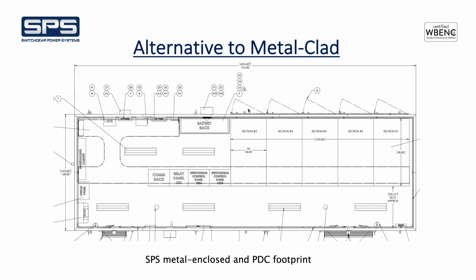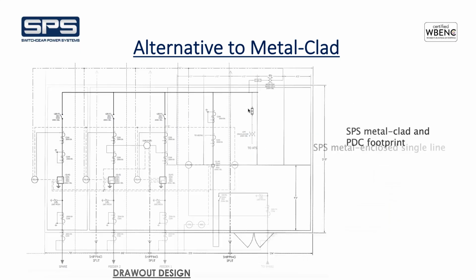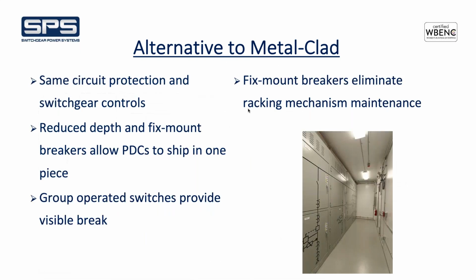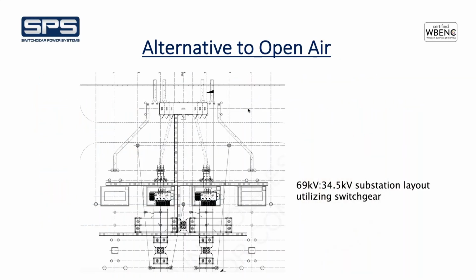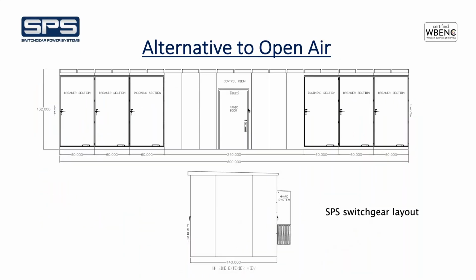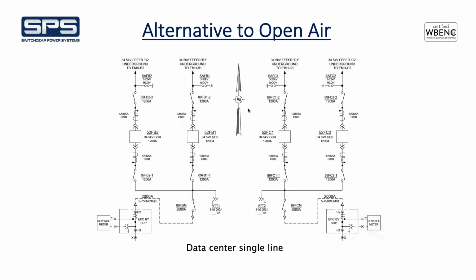The answer is, the footprint to have a line side disconnect would get a little bit deeper than the 98 inches. So in order to have 2 disconnects per breaker, which would be what this design was. This is 2 disconnects, and it went to 140 inches. Part of that was, I believe, driven by the size of the control room that they needed. So we front and rear aligned everything. But yeah, this gear right here is what they'd be talking about with a line and load disconnect on the circuit breaker.